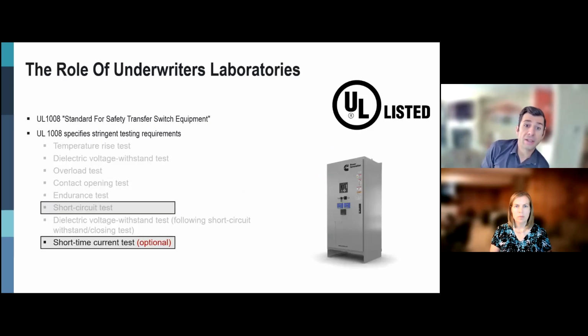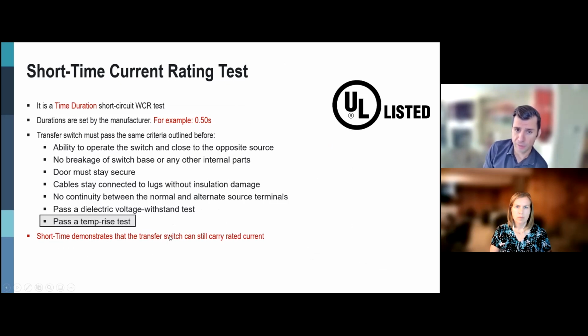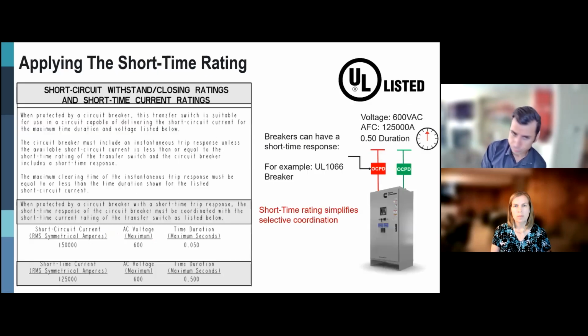The last thing I want to discuss is the short time test. The short time current test is not required by UL, but a manufacturer of a transfer switch can go above and beyond and say, I want to prove that the transfer switch not only can handle the fault current, but can still be used again in the circuit, because we must pass all the testing criteria for the WCR plus pass a temperature rise test.